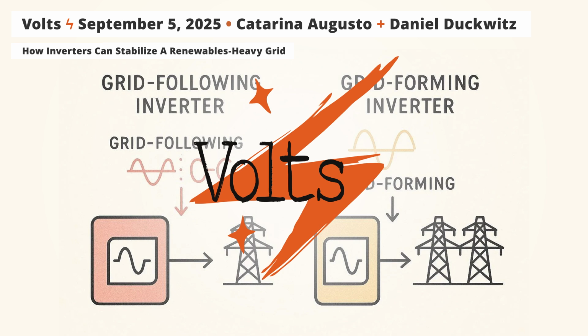There's another advantage: for a thermal power plant, to adjust output you'd have to adjust the amount of steam or fuel going into the turbine, and this takes time. That's why frequency control services, in the synchronous machine-based world, have response times of 10 to 30 seconds, which is absolutely not necessary for a battery. The battery can adjust its steady state output within half a second. So there are options to improve overall system behavior and get back to steady state much more quickly than before.